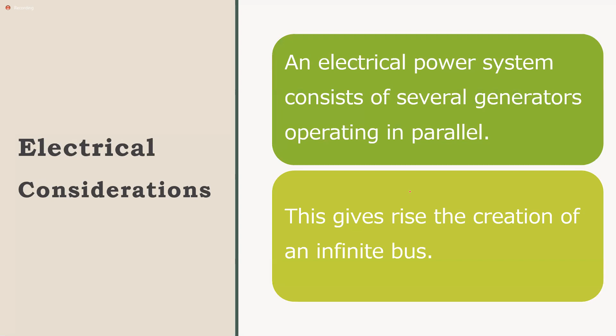So we're looking at the electrical considerations. First we talked about the infinite bus. The next thing we need to talk about is synchronization. You won't be able to supply power from two generators unless they are in sync, in step with each other. What we mean by being in step is that they must operate at the same voltage, the same frequency, and the same phase rotation or phase sequence. You can't have one operating ABC and the other ACB - they won't mesh. They must have the same phase rotation.